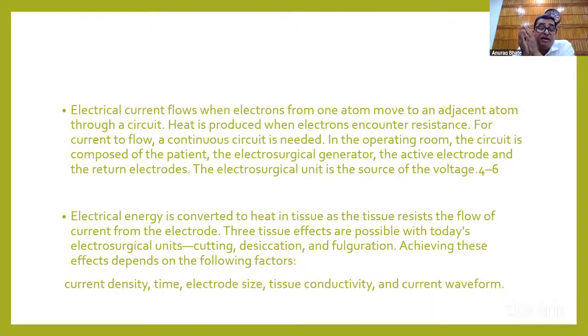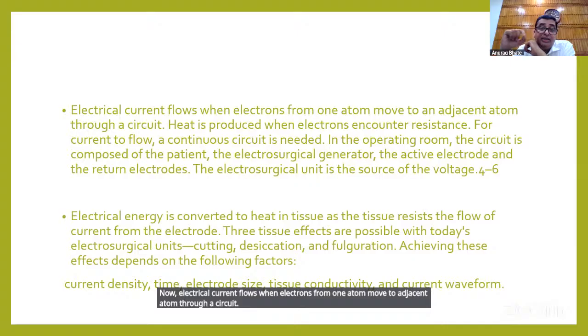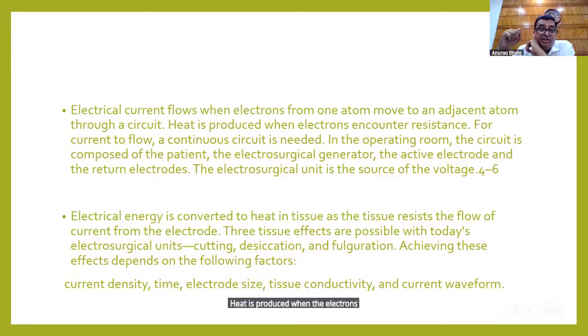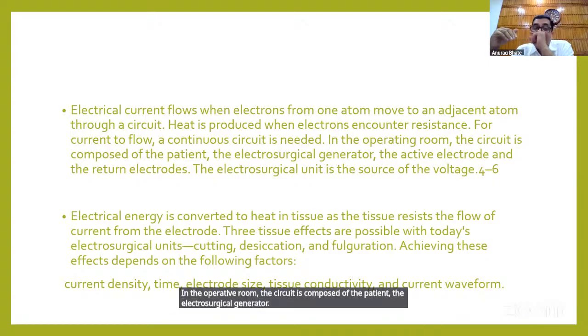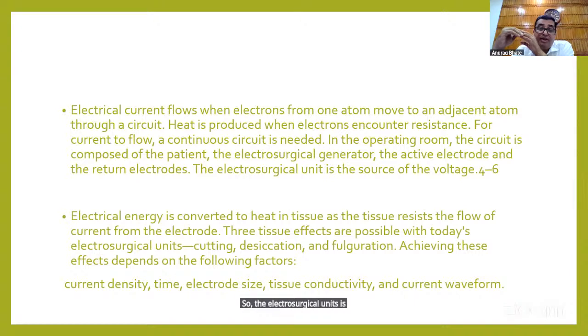Now, electrical current flows when electrons from one atom move to an adjacent atom through a circuit. Heat is produced when electrons encounter resistance. For current to flow, a continuous circuit is needed. In the operating room, the circuit is composed of the patient, the electrosurgical generator, the active electrode, and the return electrode. So the electrosurgical unit is the source of the voltage.